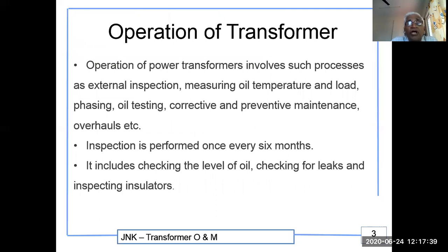We have a look at the operations of the transformer. The operations of the transformer involve such processes as external inspection, measuring oil temperature and load, phasing, oil testing, corrective and preventive maintenance. Overhauls are also included in this. Inspection is performed once in every 6 months. It includes checking of the oil, checking of the leaks, and inspecting the insulators.